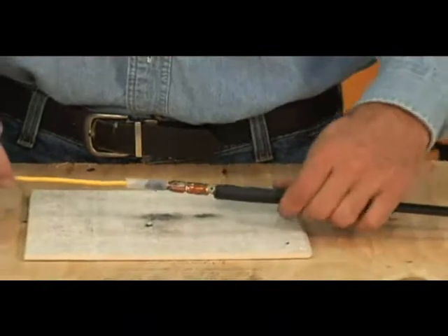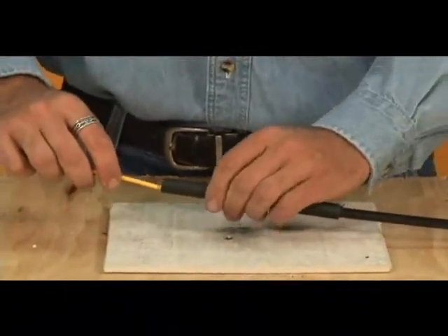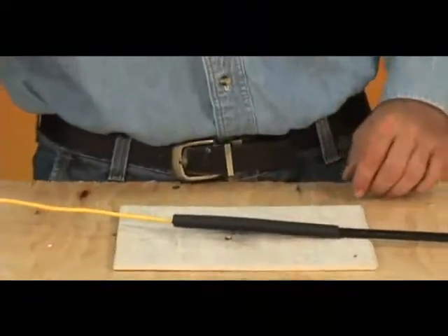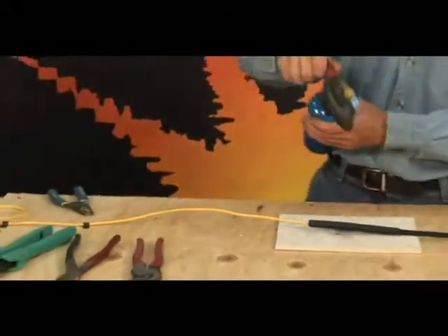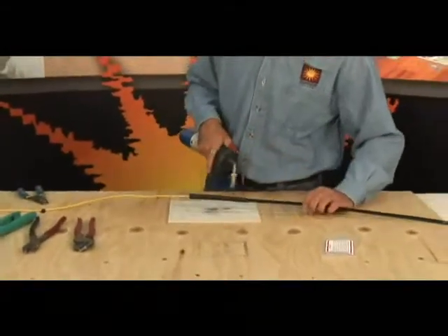When the splice has completely cooled, slide the heat shrink and center it over the splice. Use a broad soft flame torch or hot air gun to heat around the diameter of the tube to warm and shrink it. Do not scorch the tube. The shrink is complete when the adhesives ooze from between the tube and the tough cable and the cold lead.